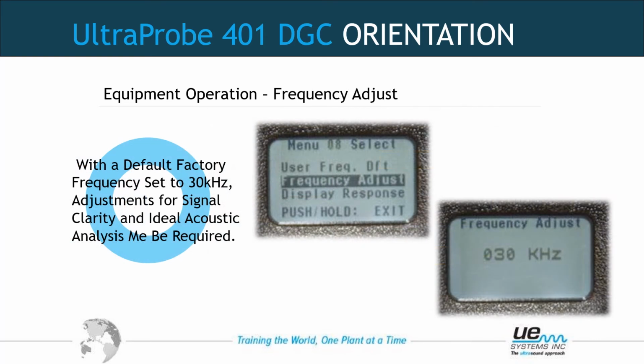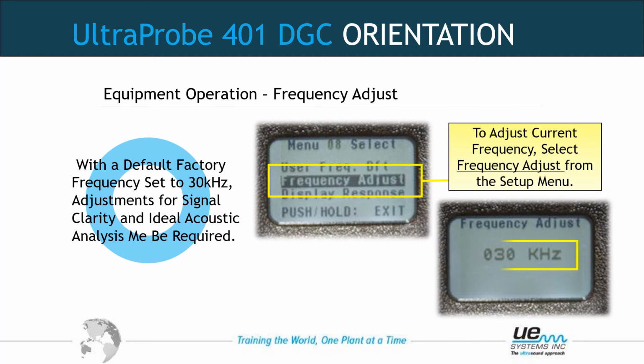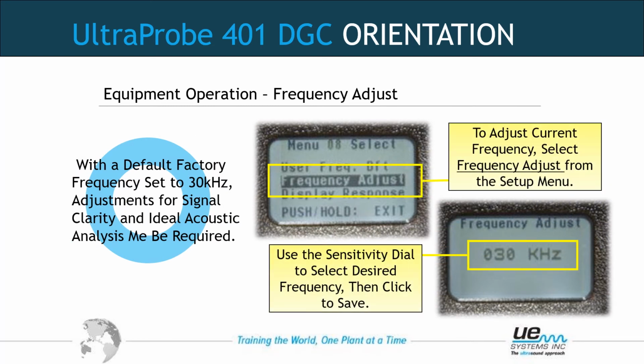Continue down that list to frequency adjust. To adjust the frequency for this particular unit, you must come into menu number 8 here and choose frequency adjust. Then you will adjust your frequency to the desired frequency you want. The range of the Ultraprobe 401 is 20 kilohertz to 100 kilohertz. That will be where the reading is taken as soon as you exit out of this menu item. Again, if the gun is set up in automatic mode, then the test point will adjust to whatever the baseline was taken at, not what you set to here.